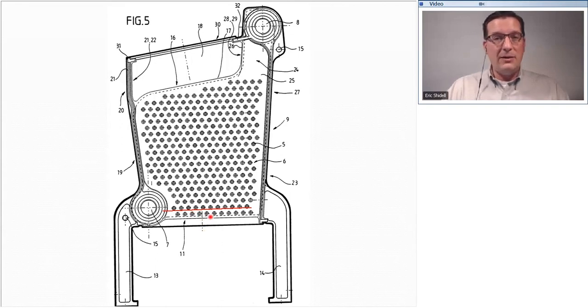That mud is kind of like an insulating layer down at the bottom. Now, there's plenty of heat transfer happening up here, but this whole boiler is going to be very energy inefficient. It's going to be an energy hog. It's going to be very poor operation. And there is absolutely no way to get that mud out of there. It's a problem. As we'll learn later, steel and iron in a boiler system is not a problem. We can have that for 100 years, and it'll never rust inside. When we get that sludge and rust, it's usually because there's been some air in the system, some dissolved oxygen in the system. We'll talk about that next week. But be aware that's the cause of that, and that there's no fixing it. That is also a really good time to start thinking about a new boiler.